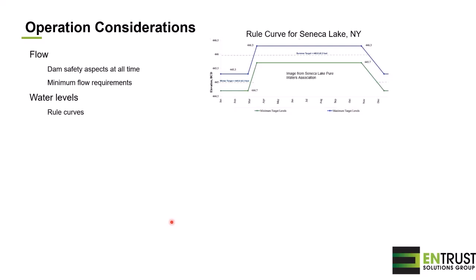Rule curves are generally created to make sure that the water projects operate in a certain condition to the benefit of everyone on the river system. So this is an example at the Seneca Lake in New York State, where the elevation before the plant will have to be within a certain target for a certain month of the year. It will increase for the summer, usually for boating reasons, and it will reduce during the fall because we know that we will need a significant amount of capacity come the spring to evacuate the water.